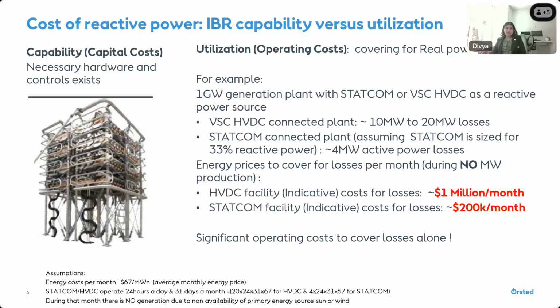For a typical HVDC system, the converter station losses could be as high as 1 to 2%. And from a cost perspective, especially in markets where energy prices could be high, you're looking at least about $1 million per month if there's no wind that month and you want to run this facility as a STATCOM for just the onshore converter station. For a STATCOM, you're looking at about $200,000 a month, assuming you've sized it to just meet today's requirement, which is basically 33% lead-lag.